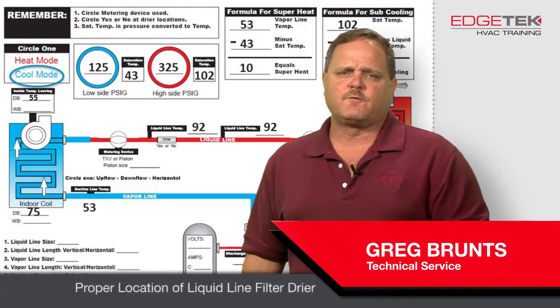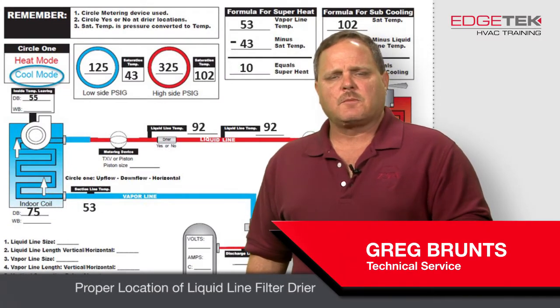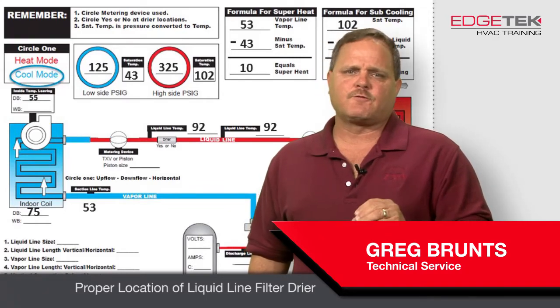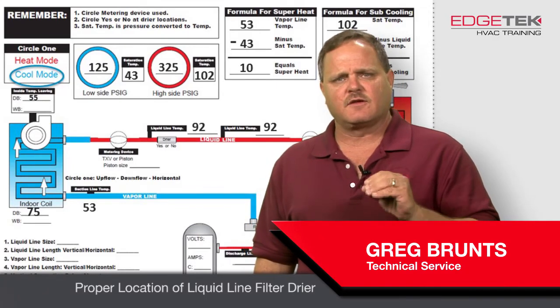Hi, Greg Brunts here with another useful tip for you. What I want to talk about today is proper location of liquid line dryers. The proper location for a liquid line dryer is always nearest to the evaporator.